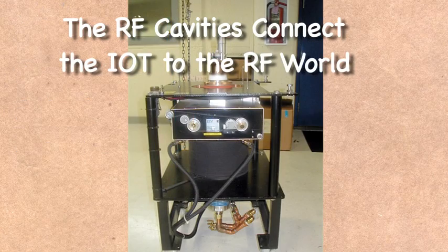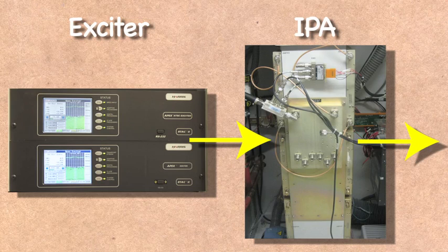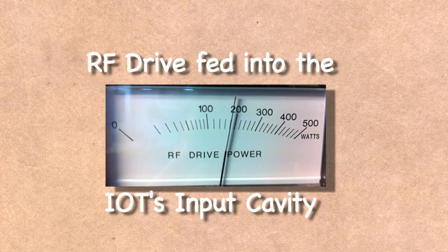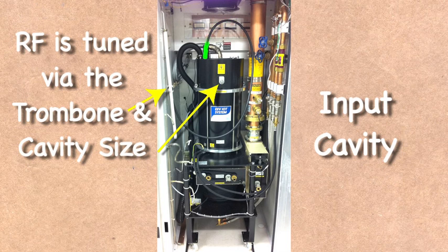Together, they connect the IOT with the RF world. Coming from the exciter and amplified by IPAs, approximately 200 watts of RF is fed to the input cavity, which is tuned for resonance and impedance matching at the operating frequency.